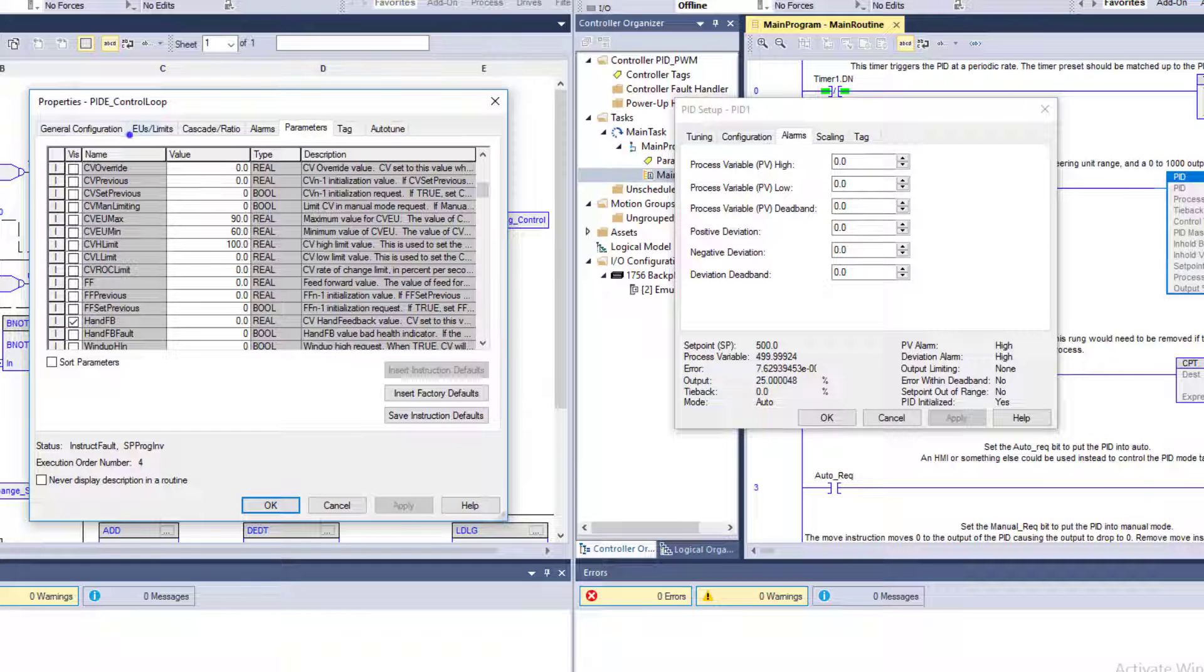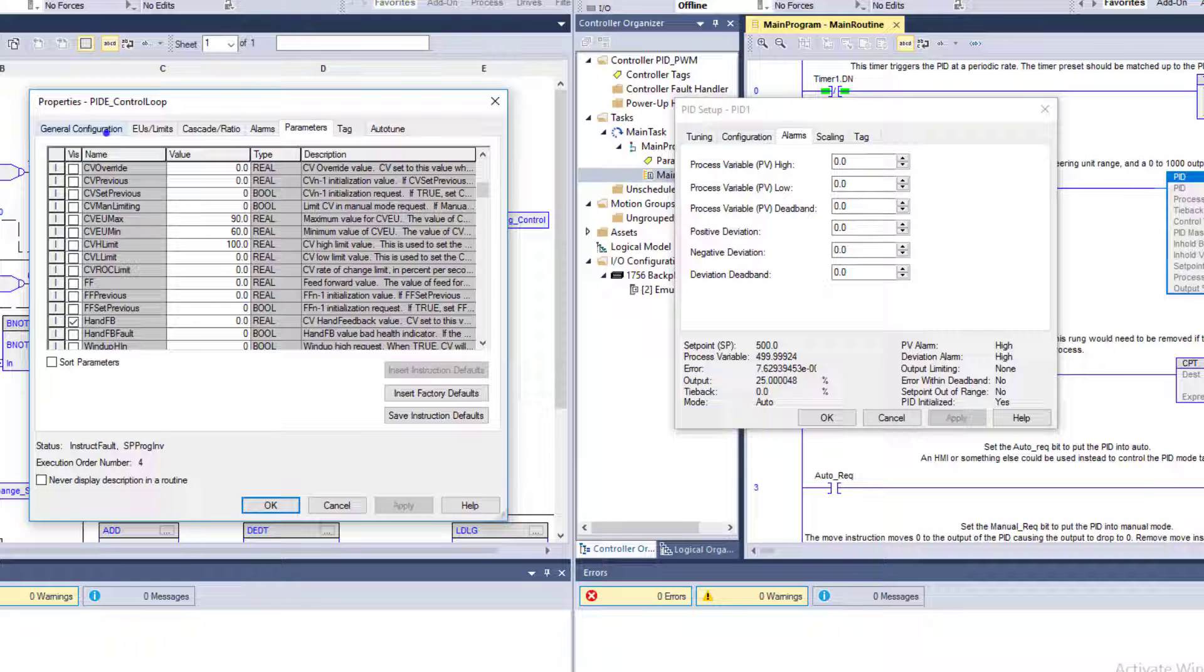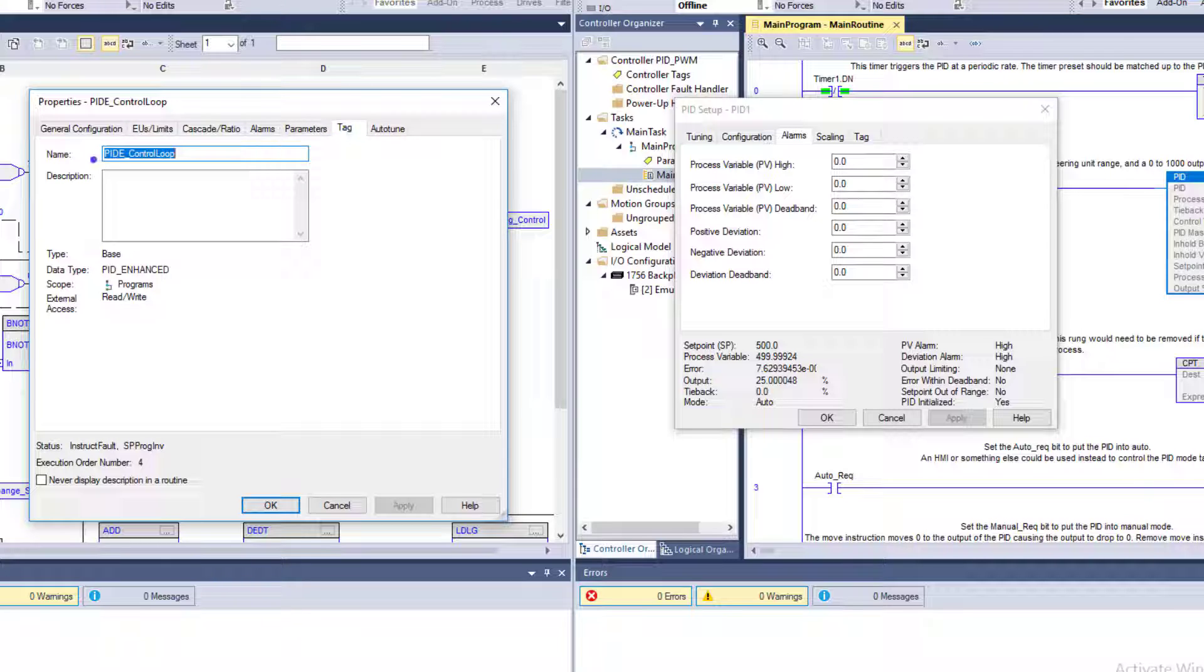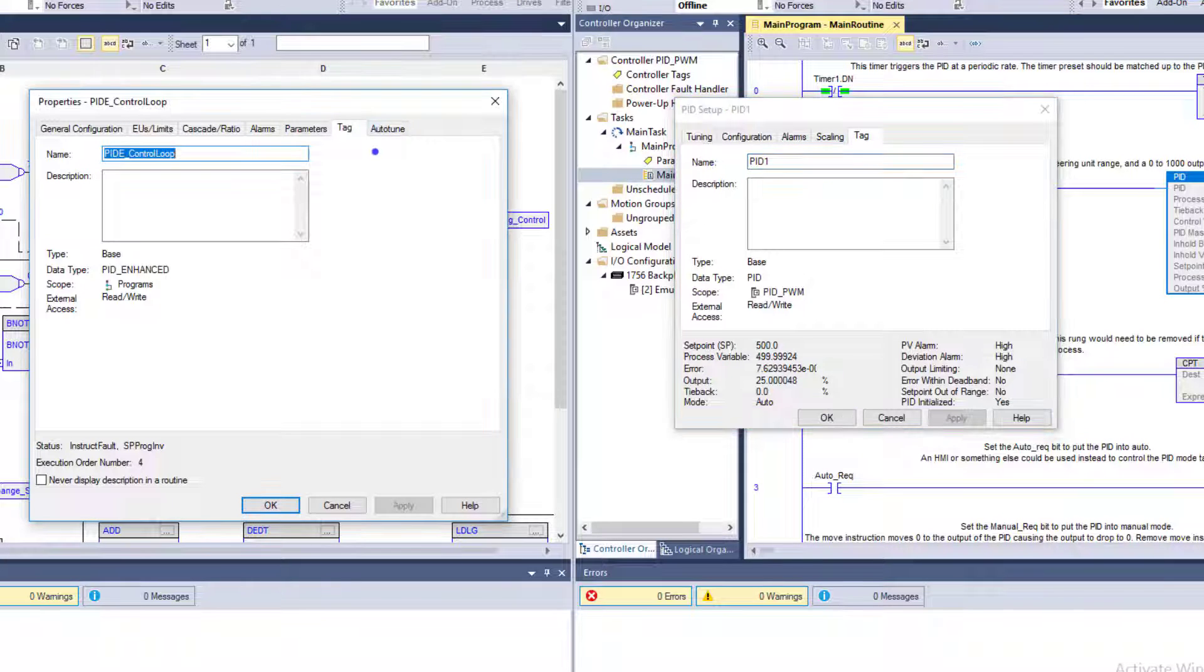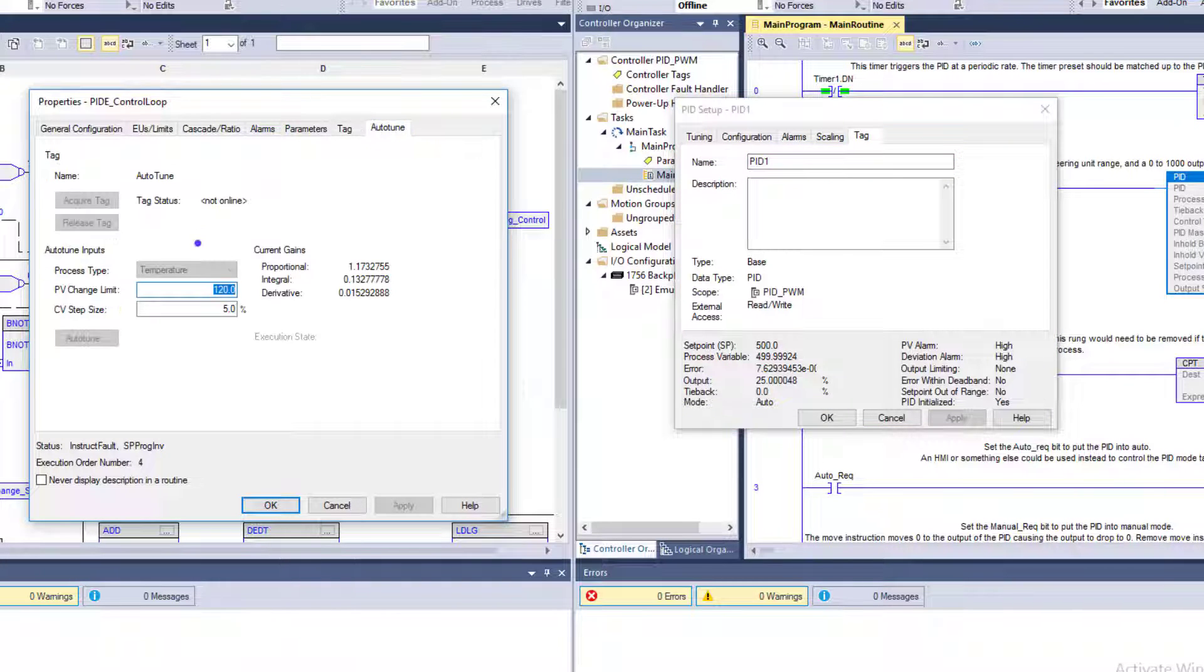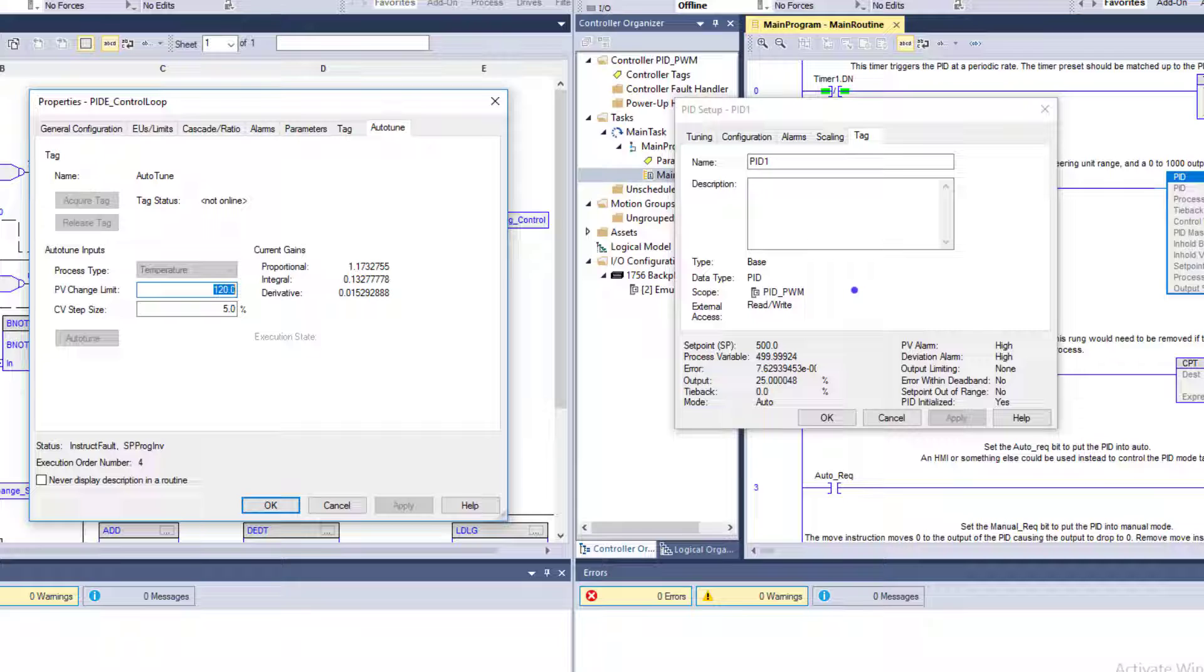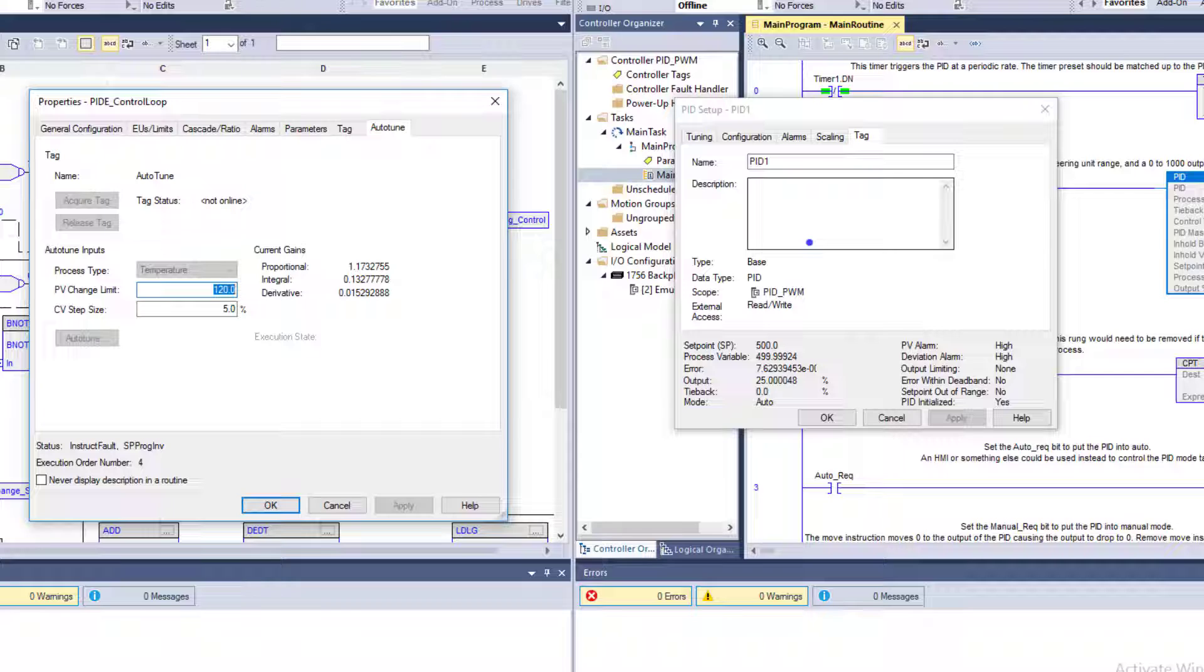Primarily, you're going to see the PIDE used inside of a function block. You will see it sometimes inside of structured text, but primarily used in function block. Your tag is going to be your tag name. Auto-tune - this is where you auto-tune inside of a PIDE. The PID does not have an auto-tune, you manually tune these. The same tuning properties basically are the same as far as the way the calculations are done. You think about independent, dependent, and the way things are done. You're going to tune these very similar, not exactly the same.